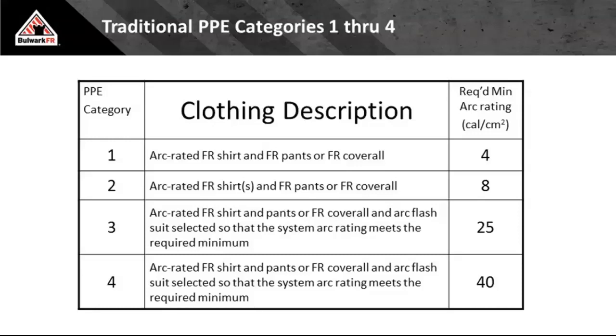So if you had an incident energy calculation of 11 calories, if you use the Cat method, you have to be in a 25 or greater flash suit. That PPE that you're wearing has to have more than 25 calories of protection in order to work on that 11-calorie box. If you use the incident energy method, what do you have to be? Just a little bit more. So you could have 11.5 calories of protection. You could climb into a 12-calorie coverall and work on that box if you use the incident energy method versus using the Cat method. The Cat method forces you into 25 calories or greater.